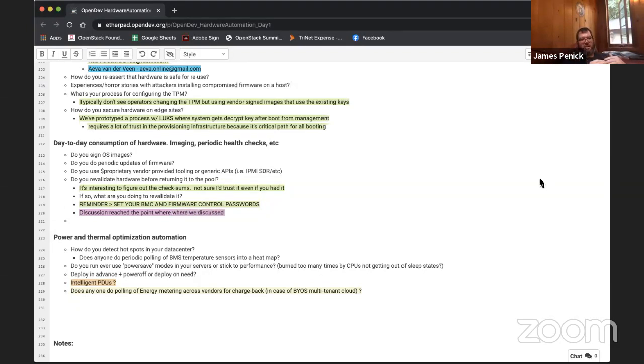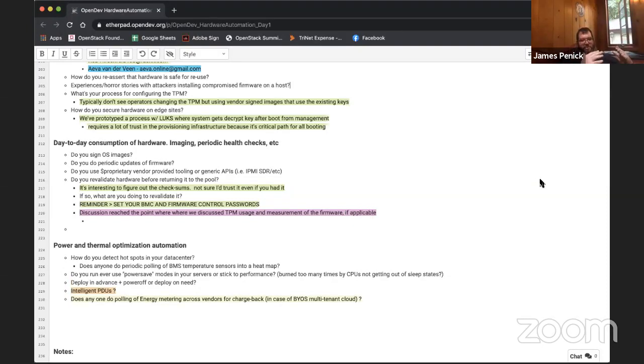So this means that the servers are the air pumps that are driving air out of the data center, which means that those are helping pull air in through those passive louvers on the outside of the building. There's also membranes behind the louvers that can have water pumped in them for a swamp cooling effect to help chill the air intake even further.